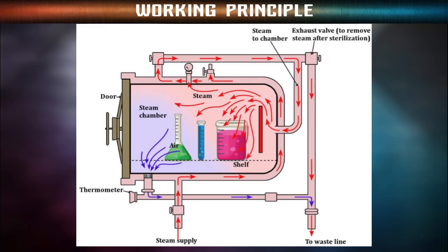Similarly, the high temperature also facilitates the rapid penetration of heat into deeper parts of the material. And moisture present in the steam causes the coagulation of proteins, causing an irreversible loss of function and activity of microbes. This principle is employed in an autoclave where the water boils at 121 degrees Celsius at a pressure of 15 psi. When this steam comes in contact with the surface, it kills the microbe by giving off latent heat. The condensed liquid ensures the moist killing of the microbes.